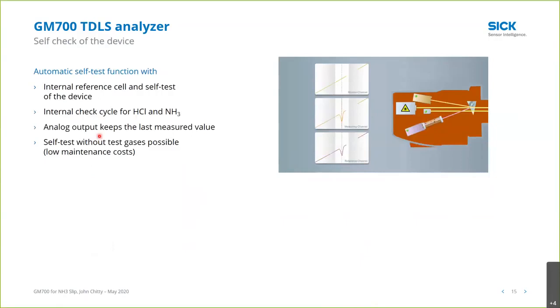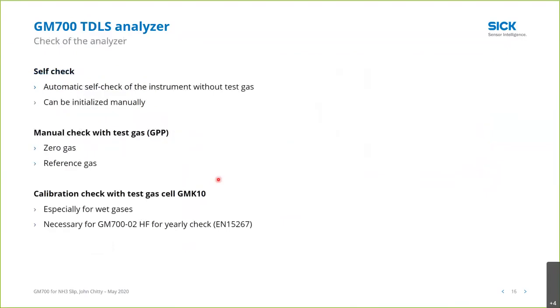That automatic self-check function, we use that internal reference cell, and that gives us a span check, and we use the internal monitor channel to give us a 0 check, and we can do a self-check. During this self-check, it keeps the analog output at the measured value. That is configurable. You can change that. And the self-check is possible without cal gases. The self-check can also be manually initialized. You may want to do this if you're doing a check of the analyzer.